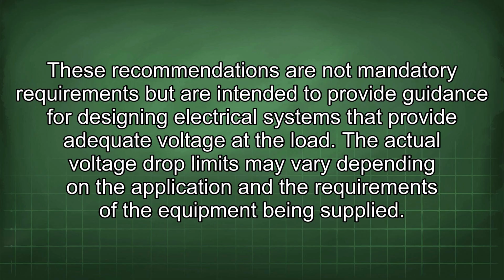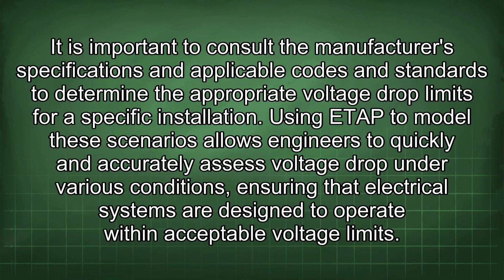These recommendations are not mandatory requirements but are intended to provide guidance for designing electrical systems that provide adequate voltage at the load. The actual voltage drop limits may vary depending on the application and the requirements of the equipment being supplied. It is important to consult the manufacturer's specifications and applicable codes and standards to determine the appropriate voltage drop limits for a specific installation.